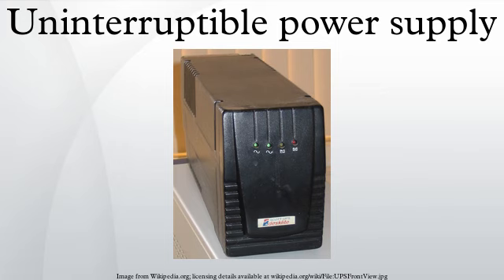Multiple redundancy. Many computer servers offer the option of redundant power supplies, so that in the event of one power supply failing, one or more other power supplies are able to power the load. This is a critical point. Each power supply must be able to power the entire server by itself. Redundancy is further enhanced by plugging each power supply into a different circuit. Redundant protection can be extended further yet by connecting each power supply to its own UPS. This provides double protection from both a power supply failure and a UPS failure, so that continued operation is assured.